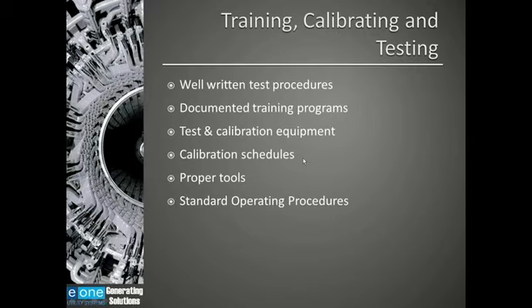You should have well-documented training programs. Again, if you don't, talk to other plants, see what they're doing. Also talk to the manufacturers of the equipment. A lot of times they offer training programs and will come into your plant to either demo the equipment or to provide training on that equipment. Make sure you have reliable and accurate calibration and test equipment. And make sure that the test equipment that you're using to test your pressure gauges and your differential gauges and your purity analyzers is calibrated and within specification. You may have to send that back to the factory in order to get it calibrated and certified.